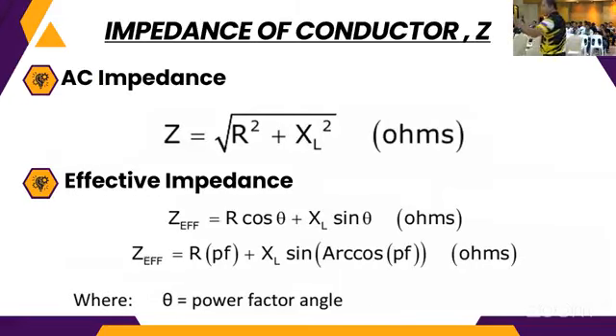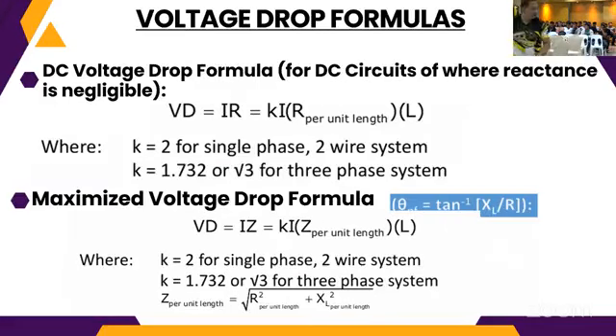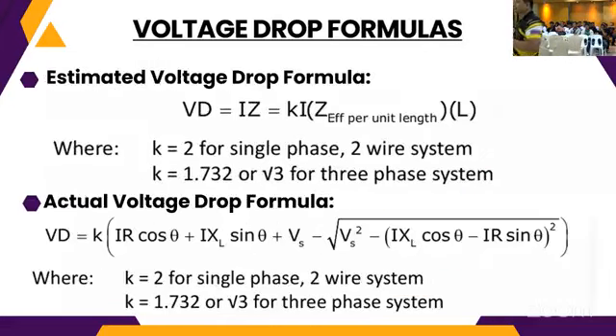So that is the formula. Effective impedance comes from the right triangle. Next. Okay, next. So the voltage drop formula. Voltage drop is equal to K times I times Z effective per unit length times length, where K is 2 for single phase, and K is 1.732, or square root of 3, for a three-phase system. So this is the actual voltage drop formula. We can derive this. If you can still remember, you can derive this voltage drop.